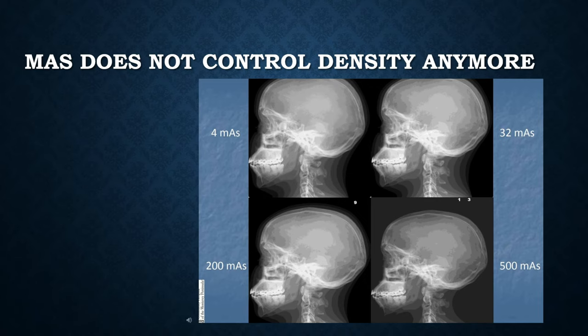Just from going from film to CR, you can increase your KV by 15 or 20. However, for Konica, it would be 5 or 10. And for most DR, you can actually use about 10 to 15 times too much mAs and still get an acceptable image.